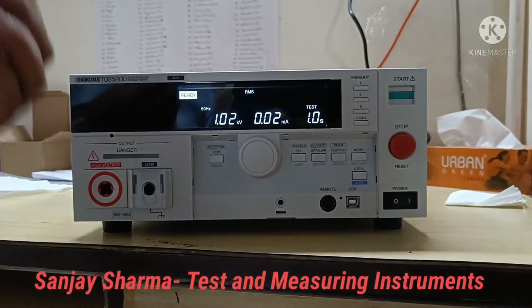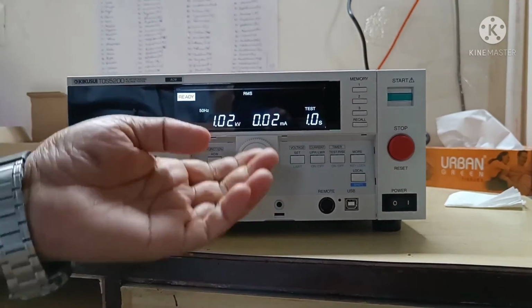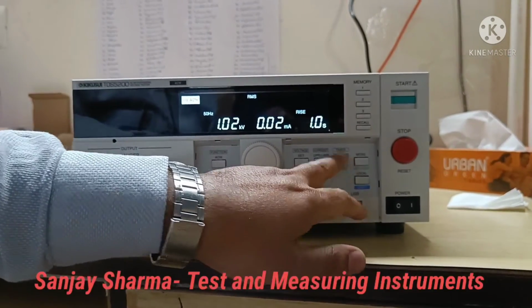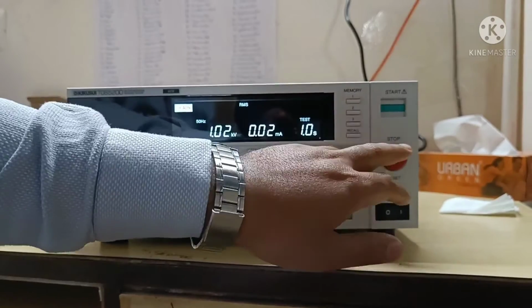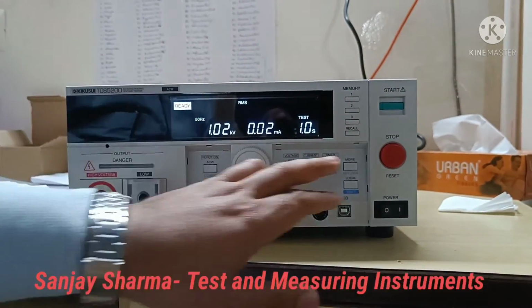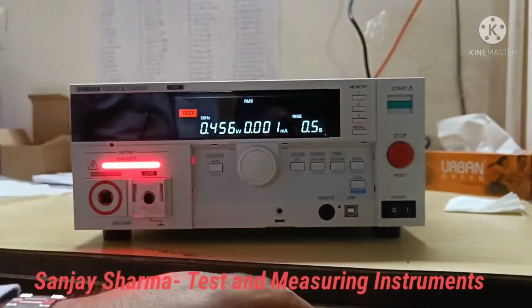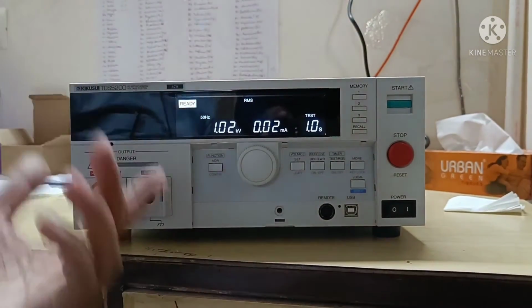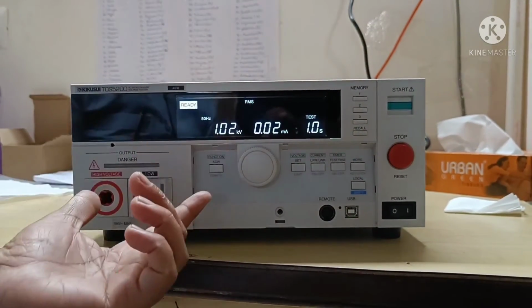So this is the overview. Right now I'm going to perform the test at 1 kV, and we have already set the test time to 1 second and the rise time to 1 second. Once I start, please carefully monitor how it performs the test. Now the rise time of 1 second is completed. One second is very little time.